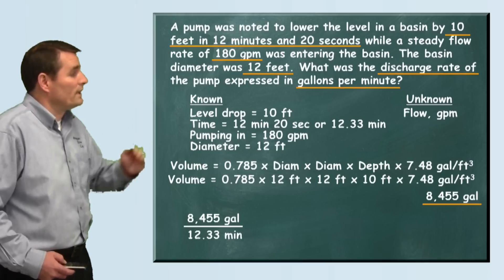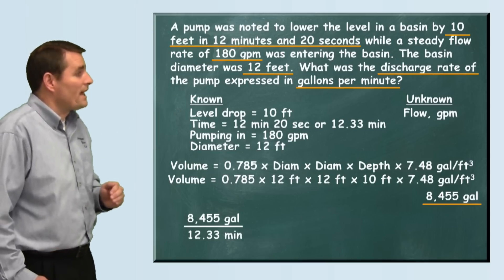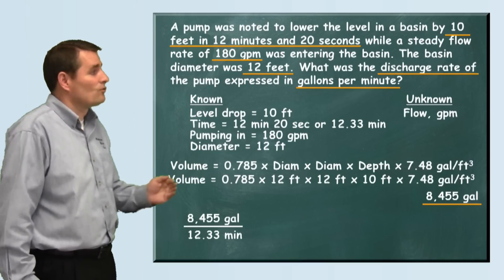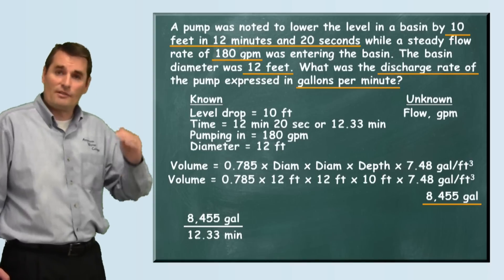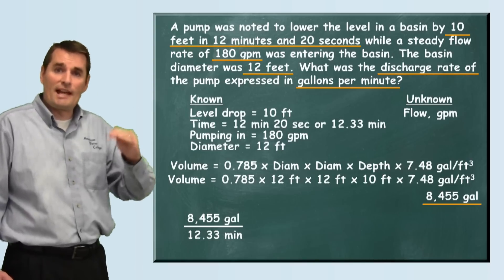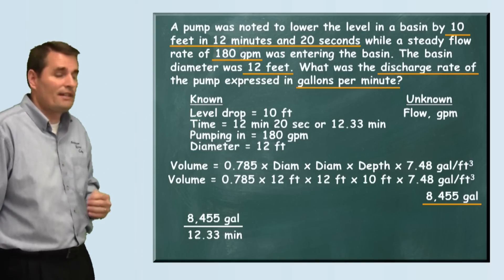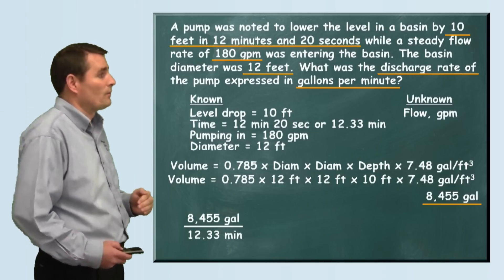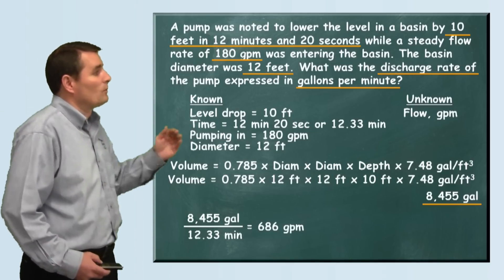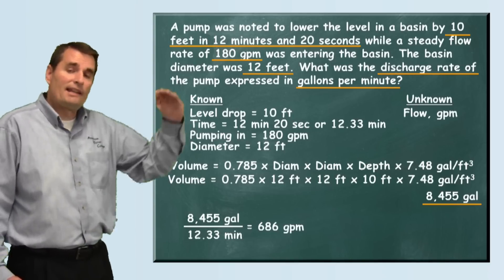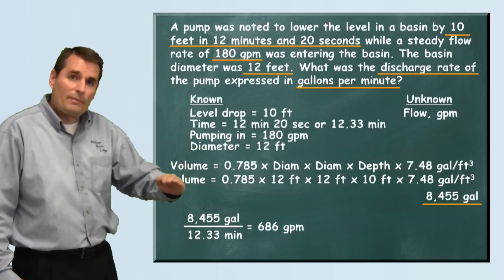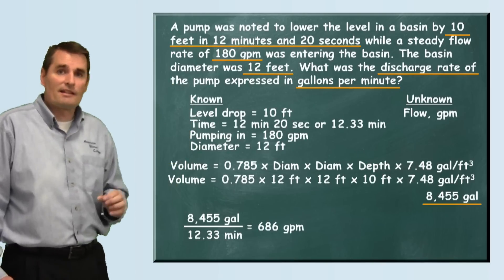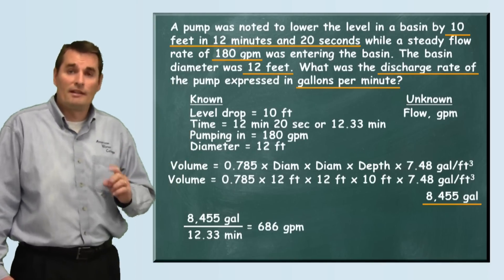We dropped that level — 8,455 gallons — in 12.33 minutes. Dividing 8,455 by 12.33 gives us our gallons per minute, and we find that the level was dropping at a rate of 686 gallons per minute.